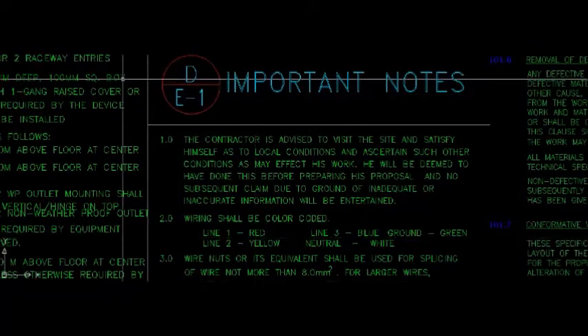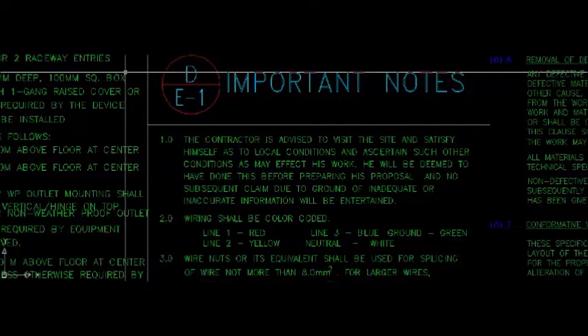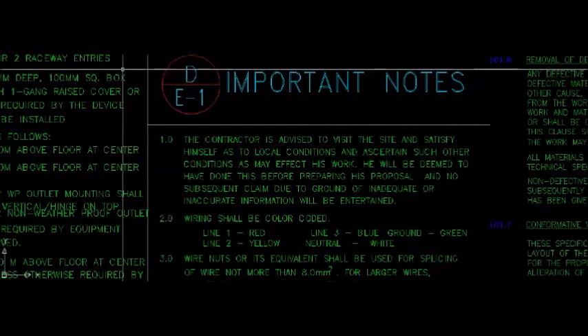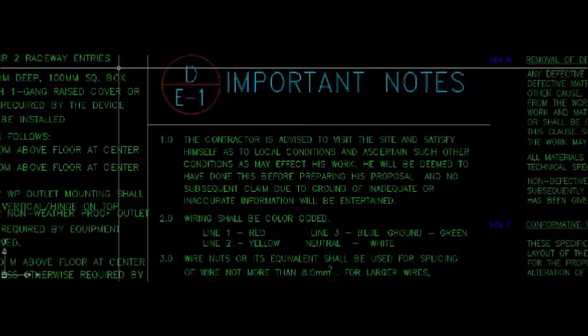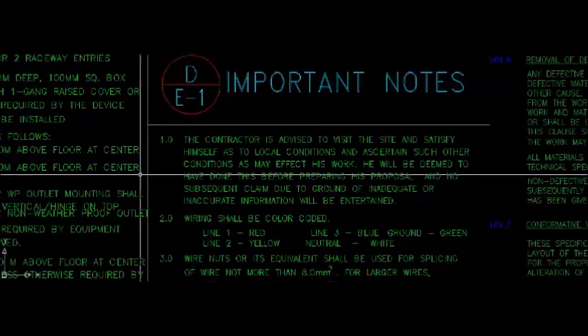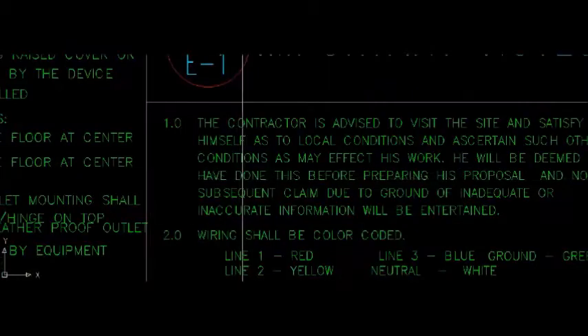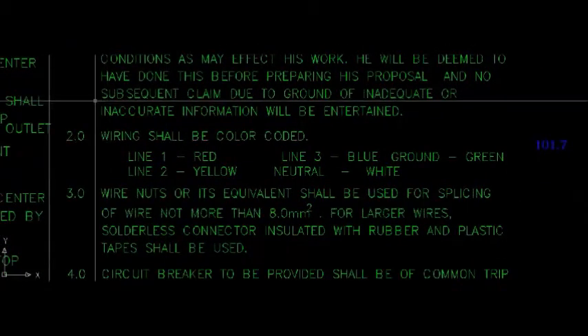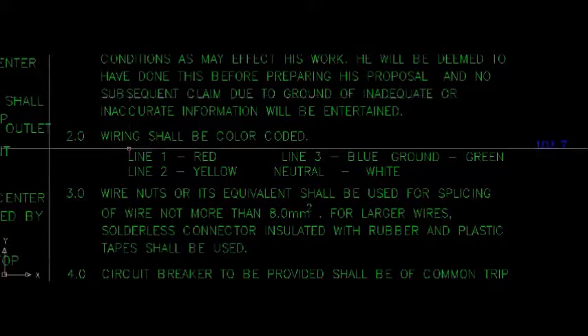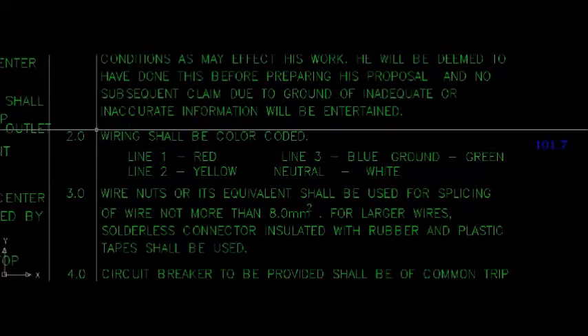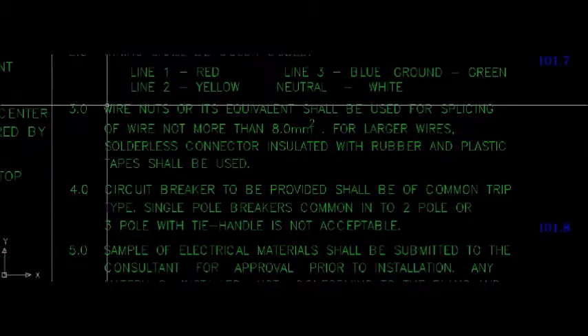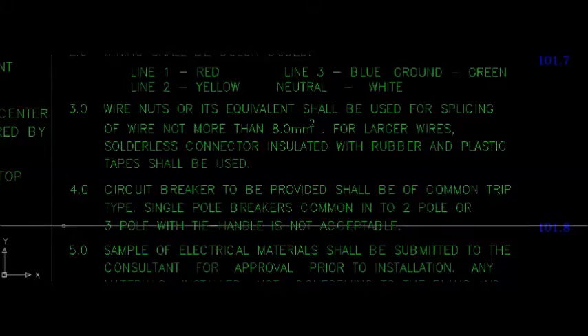Important notes. The contractor is advised to visit the site and satisfy himself as to local conditions and ascertain such other conditions as may affect his work. He will be deemed to have done this before preparing his proposal, and no subsequent claim on ground of inadequate or inaccurate information will be entertained. Wiring shall be coded. Line 1, red. Line 2, yellow. Line 3, blue. Neutral, white. Ground, green.